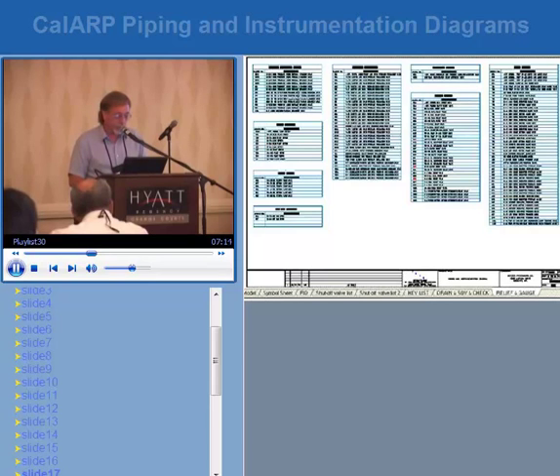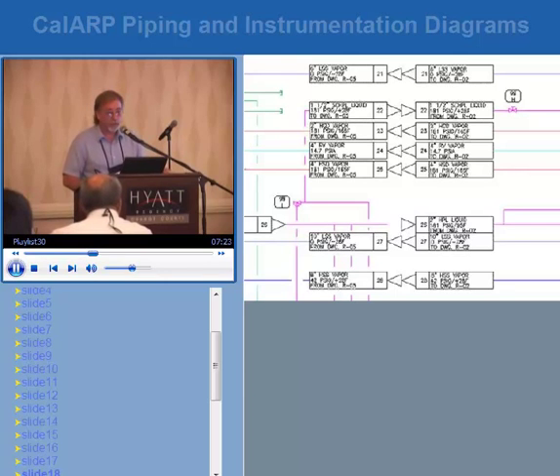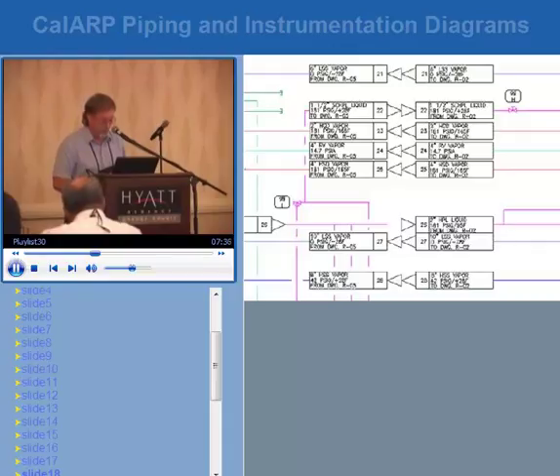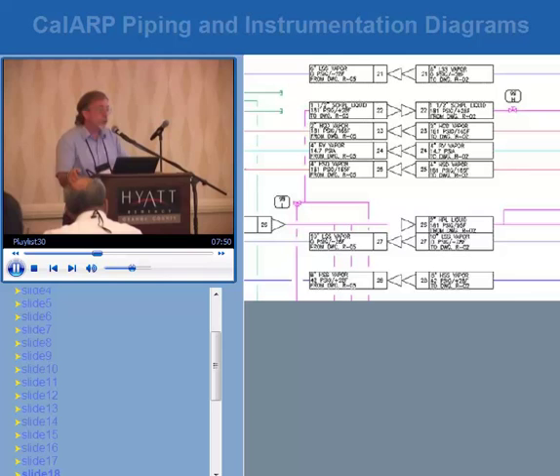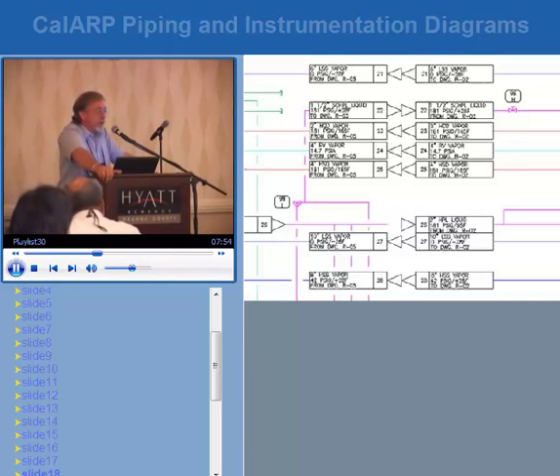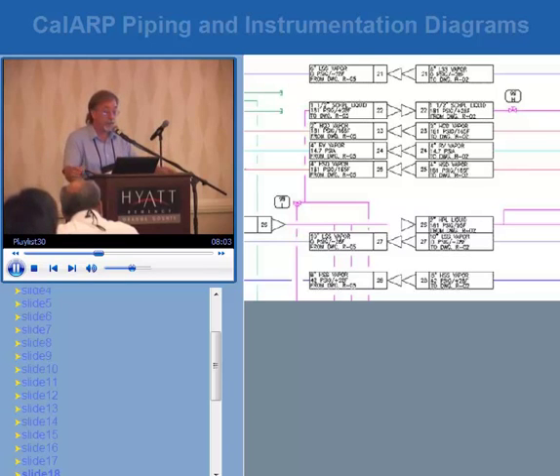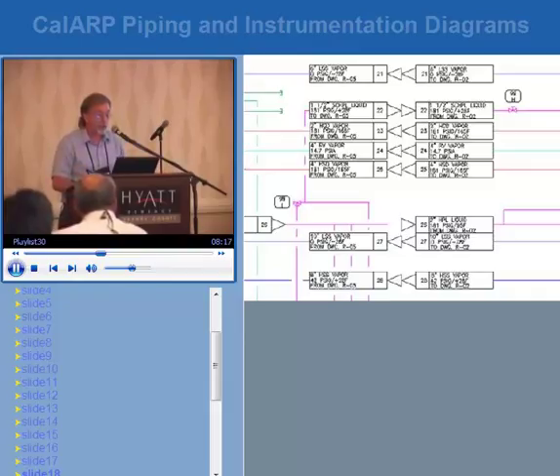When drawings get too busy to manage on one sheet, we break them up. The break points use arrows or diamonds — for example, a six-inch vapor line operating at certain conditions coming from drawing R5, line 21. The main drawing shows all lines, and then each sub-drawing details a section. As you can see, the triangle on the connector shows the direction of flow into and out of each drawing boundary, allowing you to trace a line from one sheet to the next.